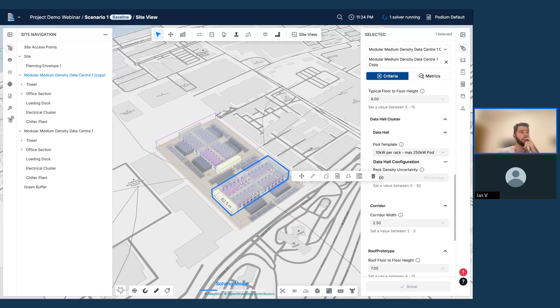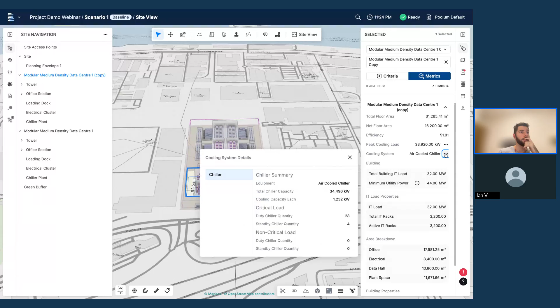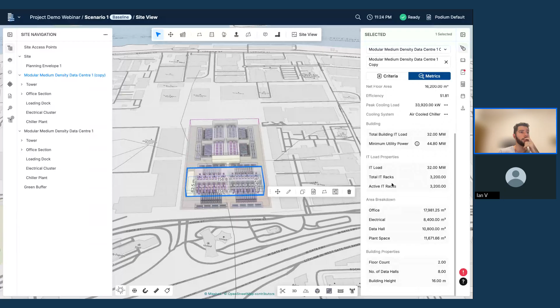What you then start getting behind all of this is a lot of metrics at the building level and at the site level. You get your areas, but not only areas, which is typically what you have in massing tools, but you start having information on your peak cooling loads, the amount of chillers in your design, the capacity of those chillers, the total IT load, and the minimum utility power to serve this building. How many racks is usually quite important as well, plus the typical breakdown of areas across the building.